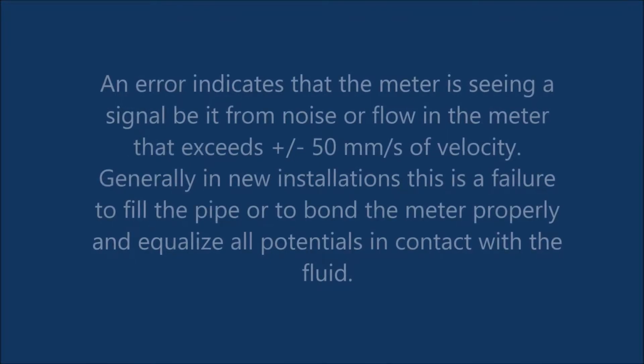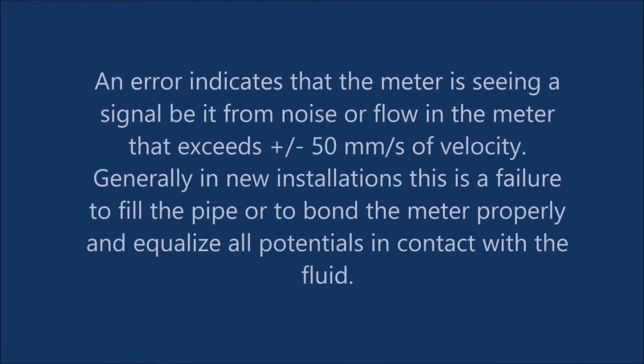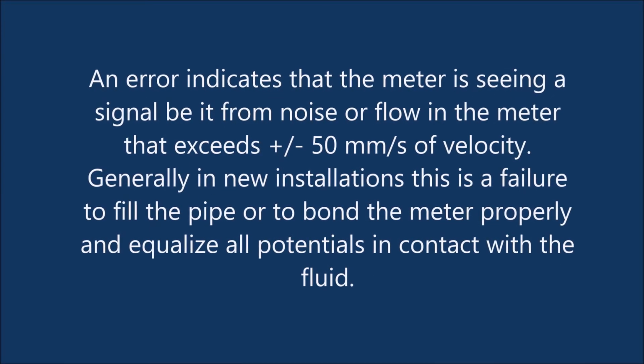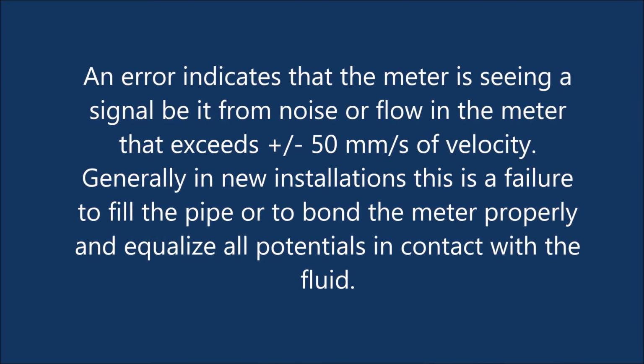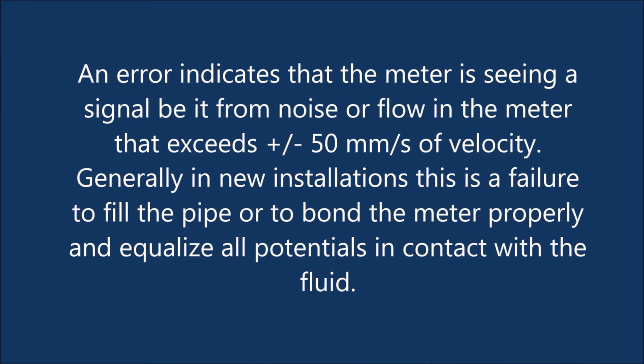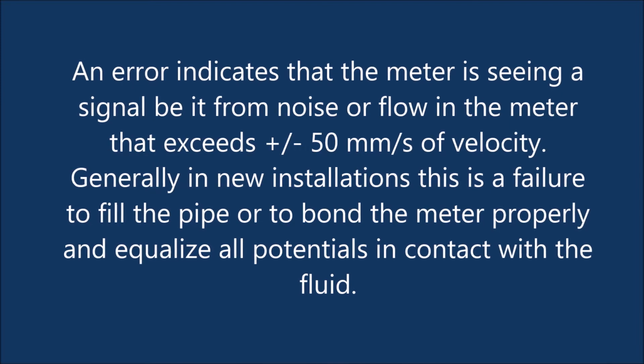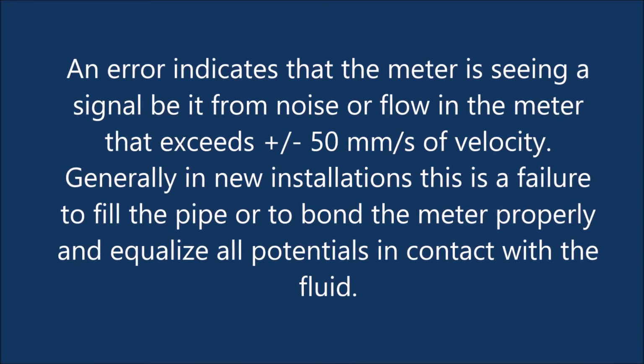An error indicates that the meter is seeing a signal, be it from noise or fluid flow in the meter, that exceeds plus or minus 50 mm per second of velocity. Generally, in new installations, this is a failure to fill the pipe or to bond the meter properly and equalize all potentials in contact with the fluid.